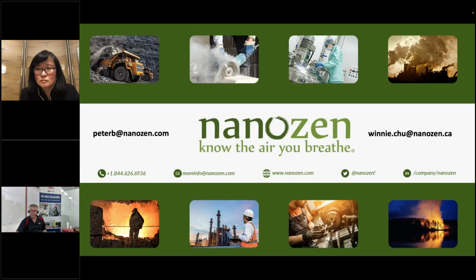The Nanozen captures a sample onto a 25mm filter for lab analysis. How does this lab result compare to a sample collected with traditional size-selective sampling? The Nanozen internal cassette has some particle loss. Most people wanted to compare to the pump and filter method, so we have been doing side-by-side tests. One side is our monitor, the other side is the cyclone. In the field the particles are not well mixed, unlike our wind tunnel where you can generate a lot of particles and mix them well. However you do the side-by-side test, you get approximately comparable results.